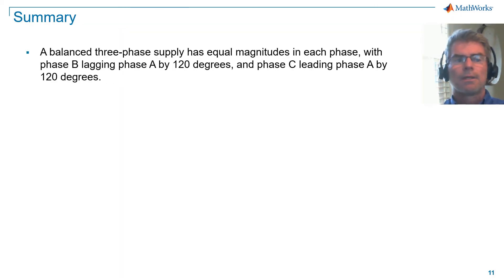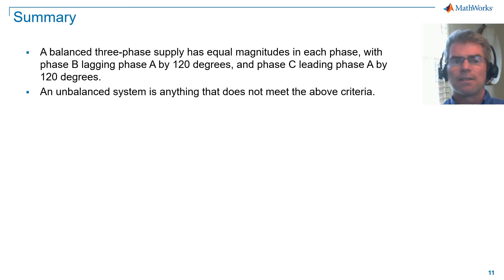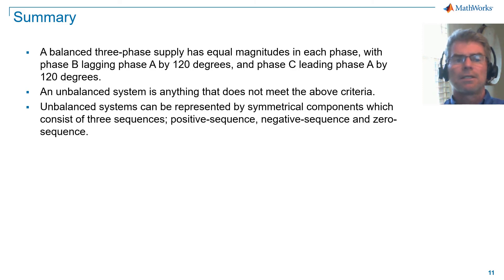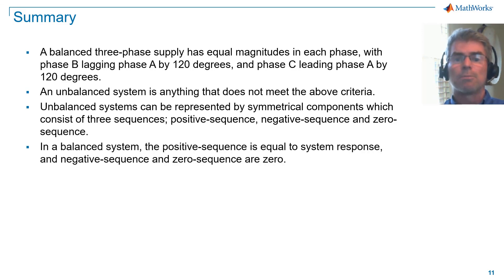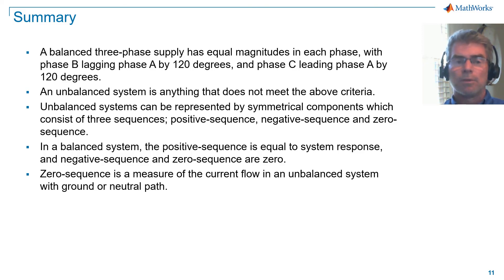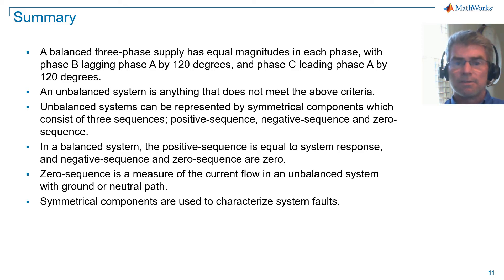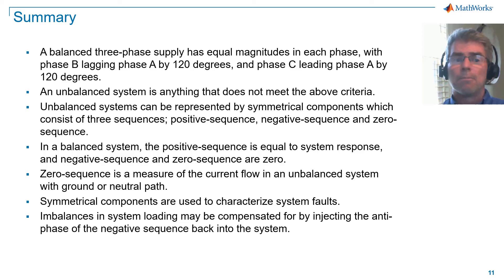In summary, a balanced three-phase supply has equal magnitudes in each phase, with phase B lagging phase A by 120 degrees and phase C leading phase A by 120 degrees. An unbalanced system is anything that does not meet the above criteria. Unbalanced systems can be represented by symmetrical components, which consist of three sequences: positive sequence, negative sequence, and zero sequence. In a balanced system, the positive sequence is equal to the system response, and negative sequence and zero sequence are zero. Zero sequence is a measure of the ground or neutral current flow in an unbalanced system which has a ground or neutral path. Symmetrical components are used to characterize faults, and imbalances in system loading may be compensated for by injecting the antiphase of the negative sequence current back into the system. I hope you found this information useful. Thank you for listening.